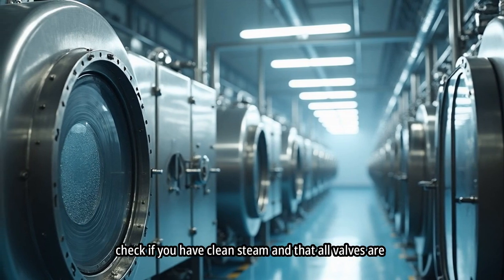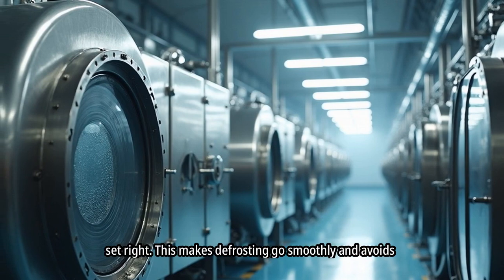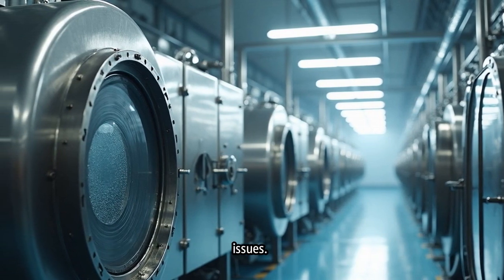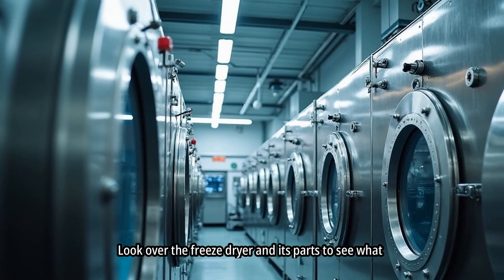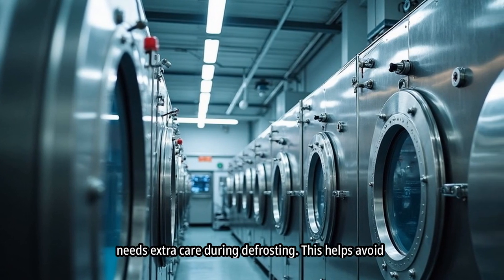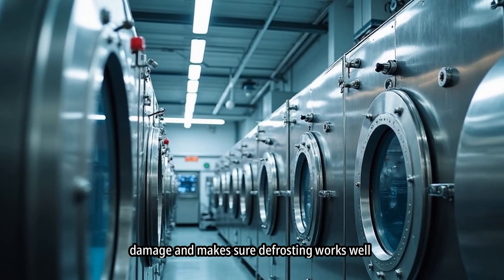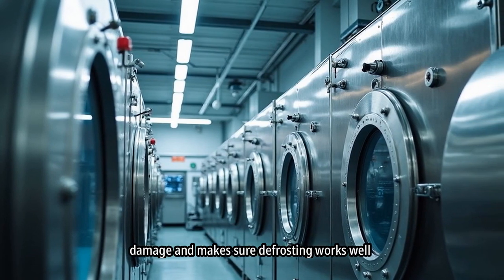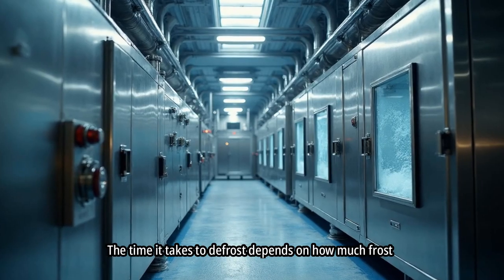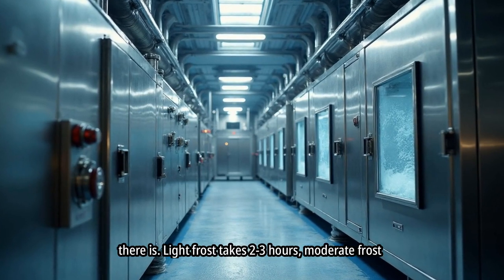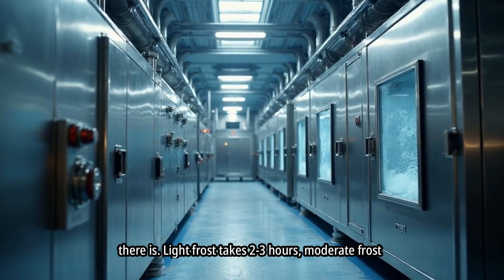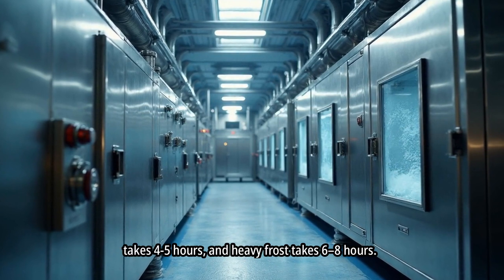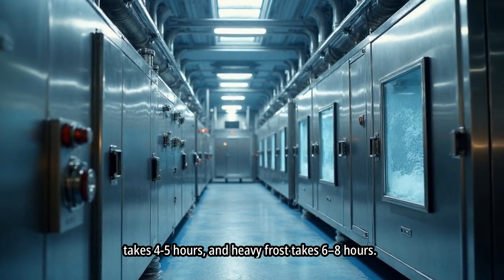Before defrosting, check if you have clean steam and that all valves are set right. This makes defrosting go smoothly and avoids issues. Look over the freeze dryer and its parts to see what needs extra care during defrosting. This helps avoid damage and make sure defrosting works well. The time it takes to defrost depends on how much frost there is. Light frost takes 2-3 hours, moderate frost takes 4-5 hours, and heavy frost takes 6-8 hours.